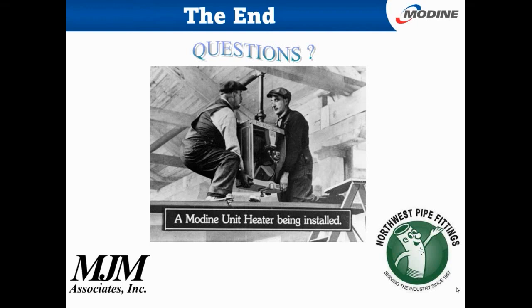So on the cubic feet, the design temp was the same as outdoor, and then the air changes. Okay, and I said 2 to 3? Yep, that's what I was gonna say. Just always use 2 to 3. It basically has to do with the cubic volume and how much air we need to supply to make sure we heat it. Put it on paper. Now, that number 2 to 3 really comes into troubleshooting ones that don't work. You gotta realize.